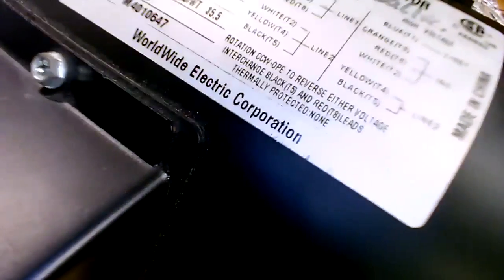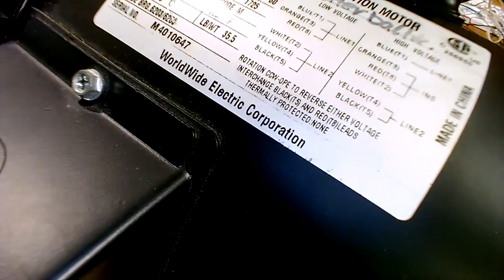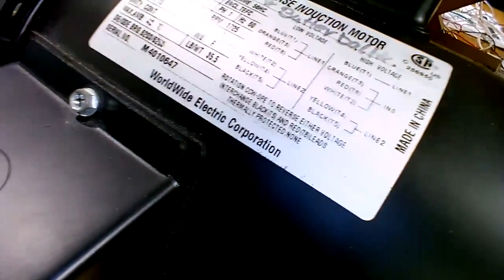Now it tells you right on the motor plate. What does it say to do down here to reverse it? Let you read that out loud. You're going to change the black and red within the motor. Now, not the incoming lines, but what's within the motor. What you end up with is this.